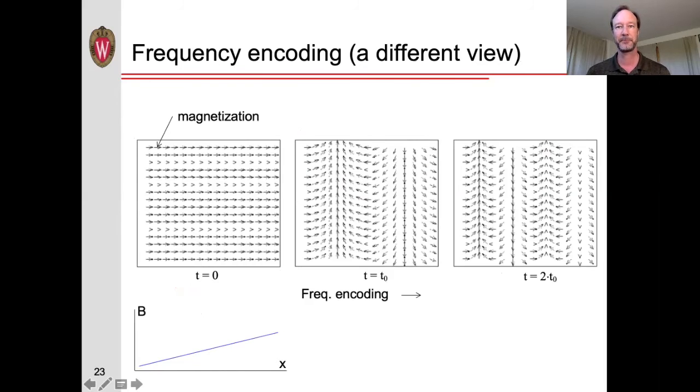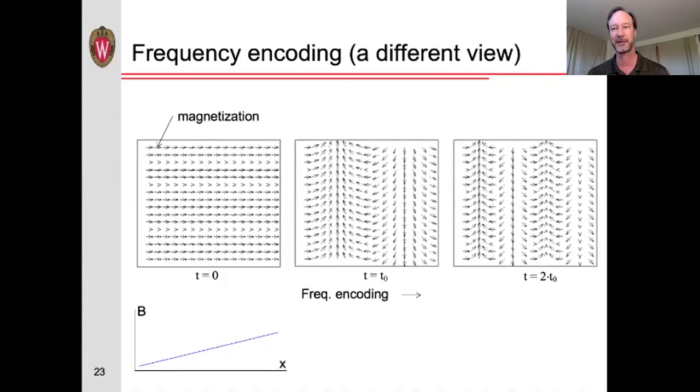With frequency encoding, we apply a magnetic field gradient while we acquire the signal. If we look at the magnetization in different parts of the image, as represented here with these set of arrows, then initially after excitation, all of the spins are pointing in the same direction. But a short time later, the spins farther along in the x direction will be precessing a bit faster and will have gotten ahead, while those in the opposite direction will have gone more slowly. So over time, the magnetization vectors are getting twisted up in the x direction.